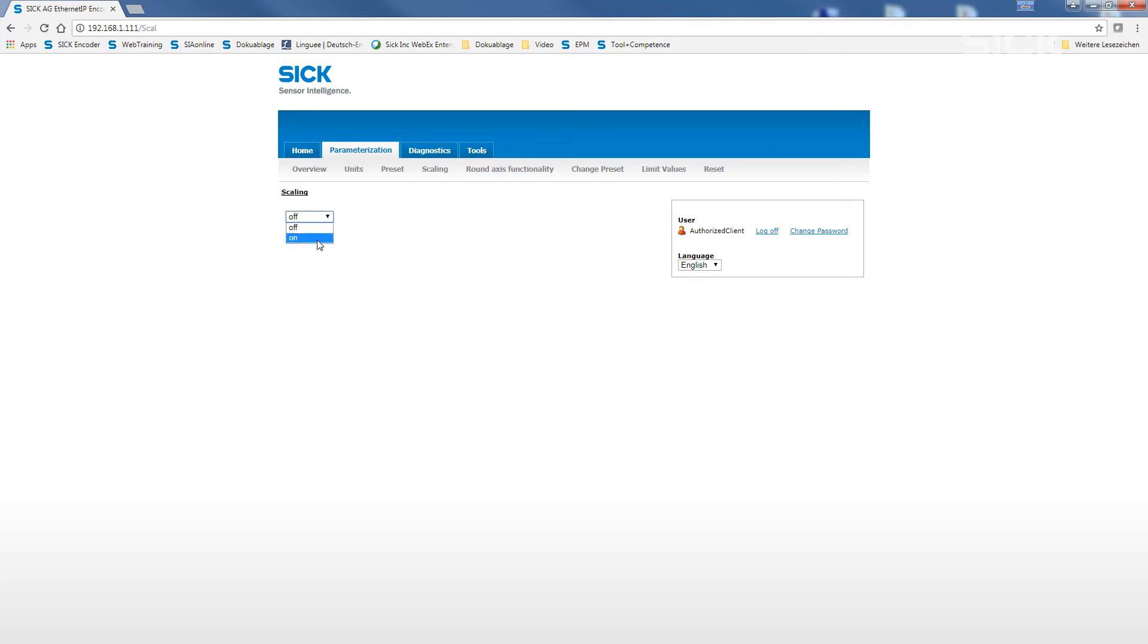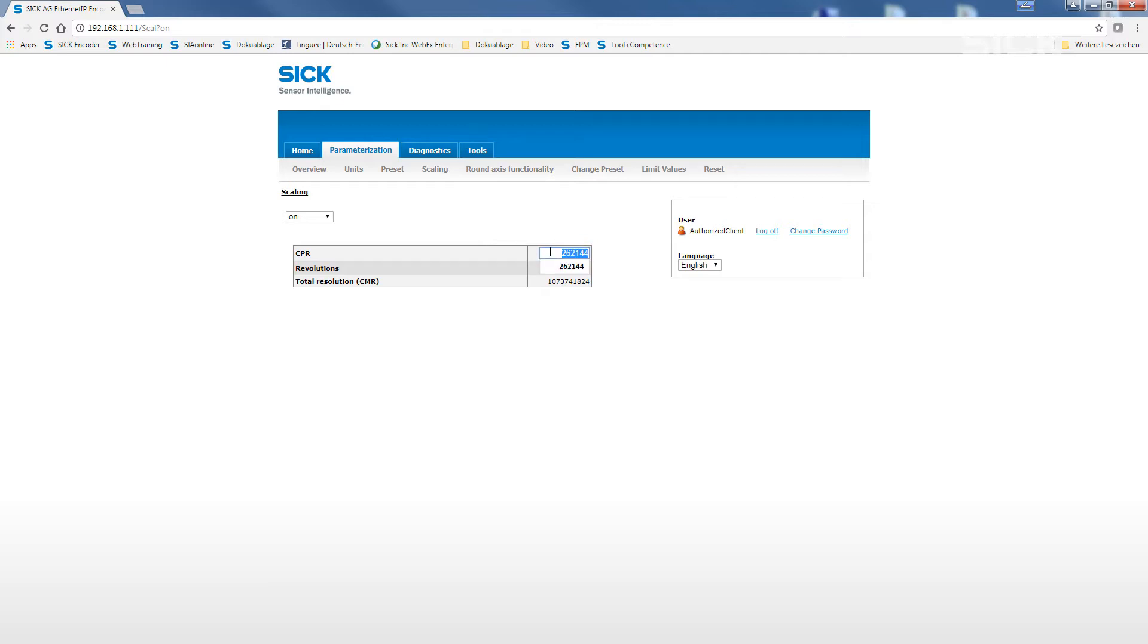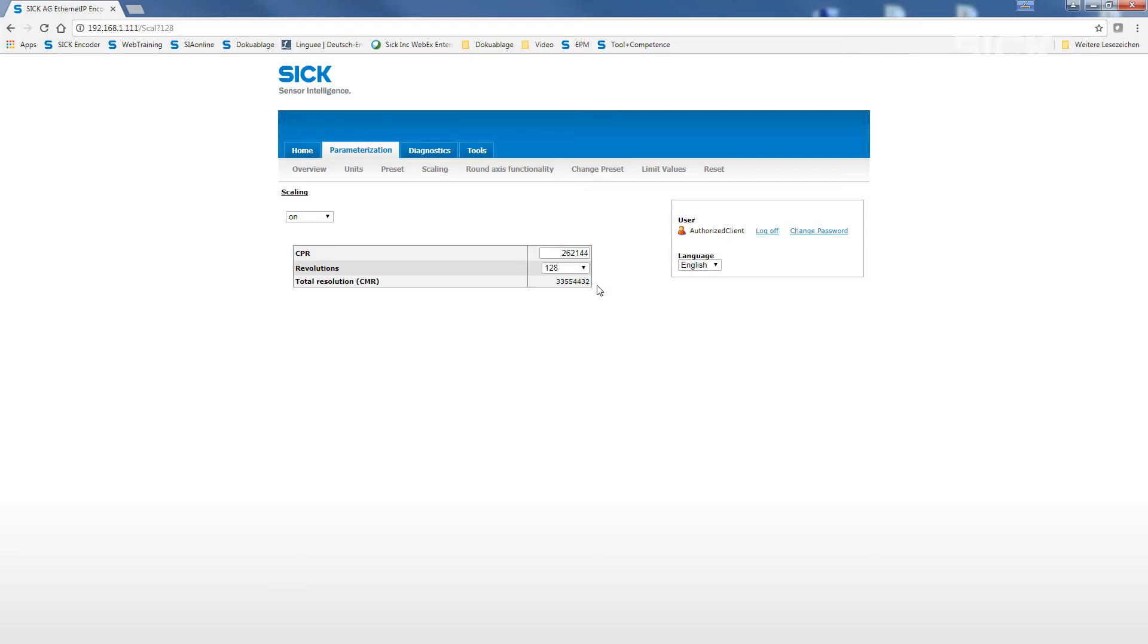Here, we have the possibility to define the counts per revolution with any integer number up to the maximum resolution. In addition, we can then adjust the number of resolutions in binary steps. The multiplication of both values results in the total resolution.